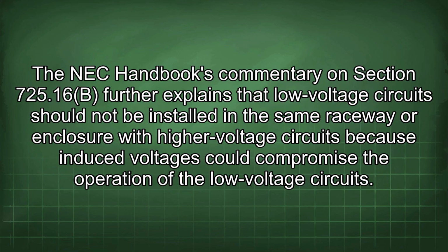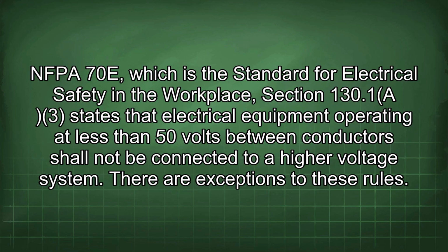The NEC Handbook's commentary on Section 725.16(B) further explains that low-voltage circuits should not be installed in the same raceway or enclosure with higher voltage circuits because induced voltages could compromise the operation of the low-voltage circuits. NFPA 70E, which is the standard for electrical safety in the workplace, Section 130.1(A)(3) states that electrical equipment operating at less than 50 volts between conductors shall not be connected to a higher voltage system.